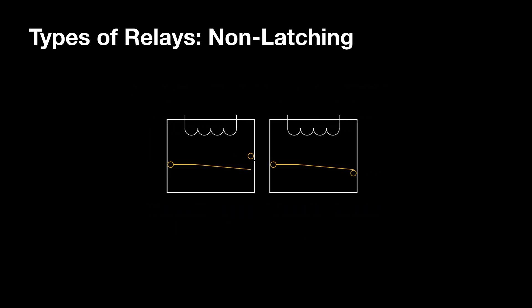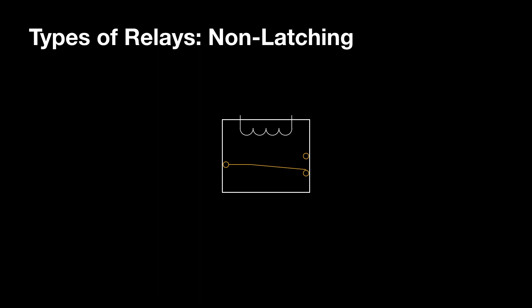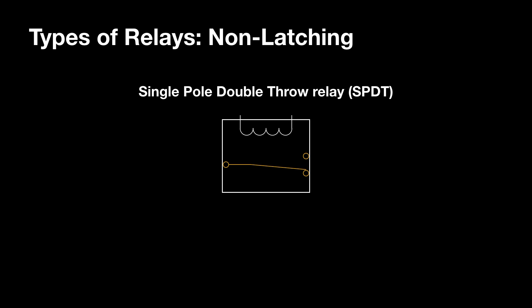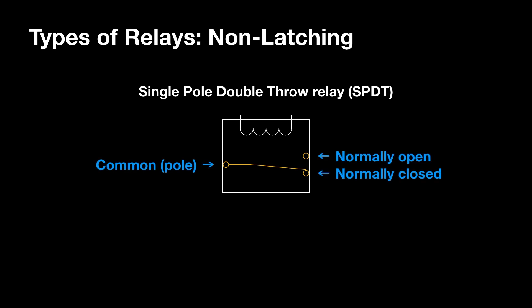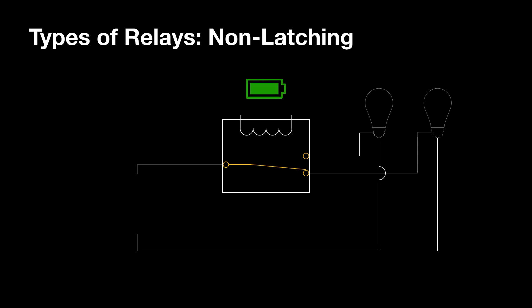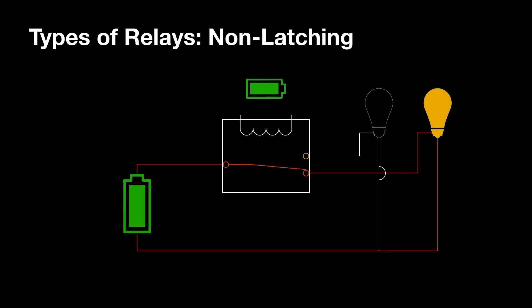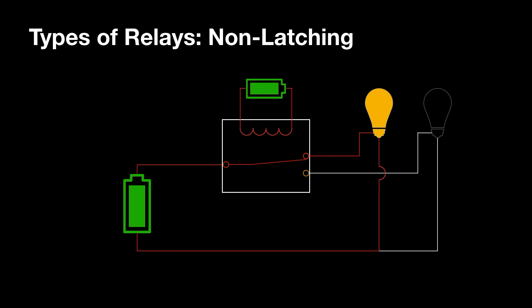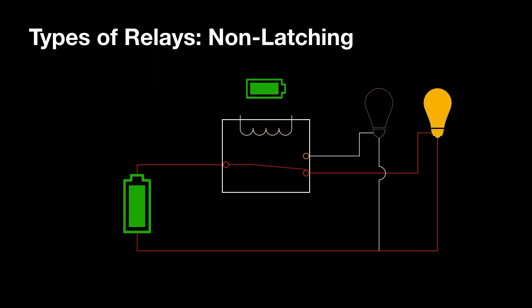Combining these two variants results in a relay that has two contacts for the armature to throw itself against. This is a single-pole, double-throw relay. The pole is now called the common terminal because no matter what state the relay is in, the armature is always connected to it. When we put this relay into a circuit with no power to the coil, we see that one of the bulbs lights up. If the coil is then energized, the bulb connected to the normally closed contact turns off, and the other one turns on.